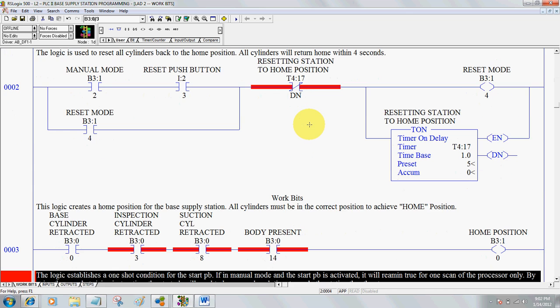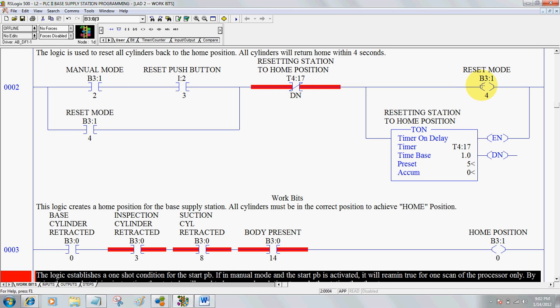The next thing is to create a reset mode. My logic says I must be in manual mode and I must push the reset push button. As long as those are true, the reset mode becomes true, which also starts a timer. The reset mode seals in — known as a seal-in or latching circuit — and after five seconds the timer's done bit opens and breaks the latch. So the reset PB is true, reset becomes true, it seals in, and after five seconds the latch is broken. This bit remains active for up to five seconds.